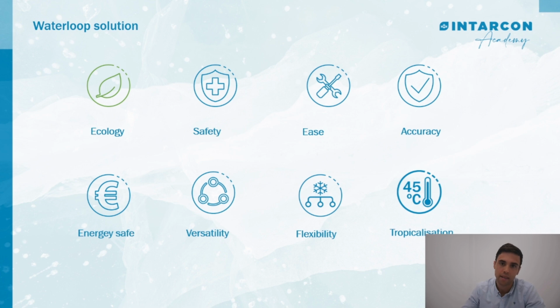The Waterloop solution provides 8 key benefits for all of the stakeholders. The first one will be ecology, reducing the R290 refrigerant charge. We minimize the risk of leaks and reduce the environmental impact. Next one, safety. The decentralization of refrigeration production guarantees high availability of cold along the system. Ease of installation, simple installation with pre-charged units and a low pressure water loop installation. Accuracy, we use optimum adjustment of temperatures and power for each application, each cool room or each workroom.